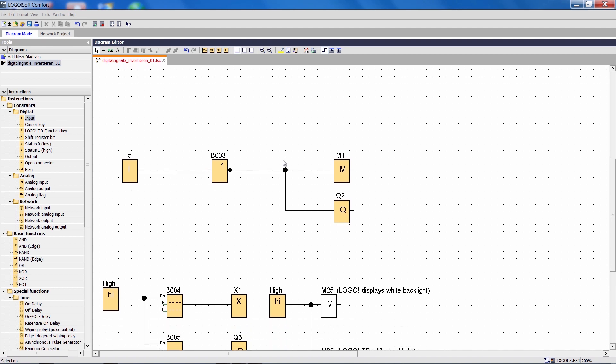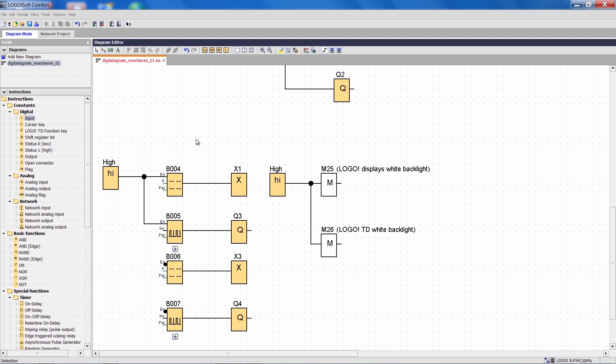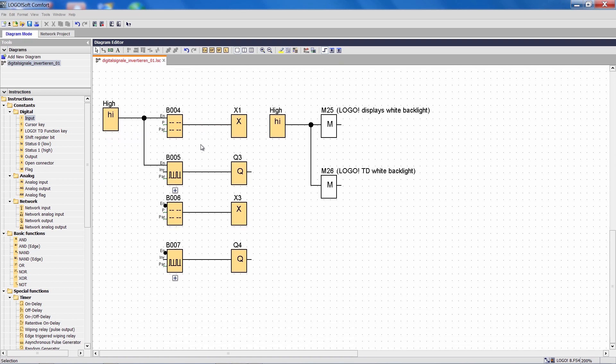When is it best to use that? There are lots of function blocks I have to activate. If I want these permanently activated, then I will generally have to use an input function block HIGH. I can get the same result as shown here if I simply negate the ENABLE pin. That will leave the function block permanently activated.